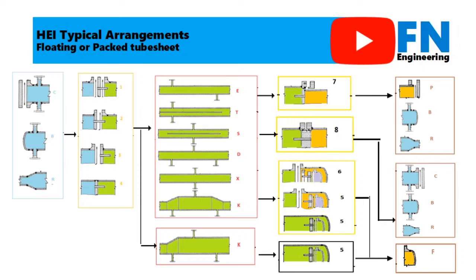For example, type 7 can only be paired with type P, type B, or type R. Type 8 can only be paired with type C, type B, or type R. Moreover, type 5 and type 6 can only be paired with type F or floating head.